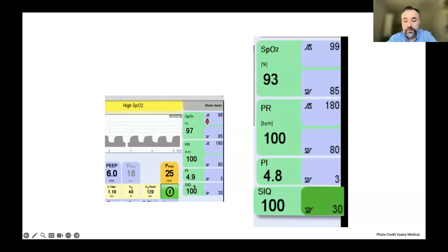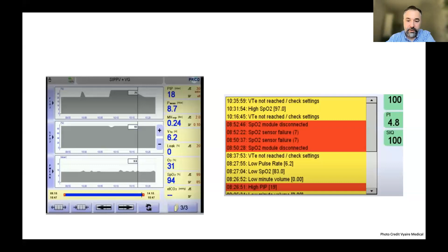This is the log of problems that can be potentially recorded by the ventilator. So if there are some problems, you can check that retrospectively, and it's also helpful to look at the trends. Here you can see the trends of the FiO2 and the SpO2. A lot can be checked versus other parameters that are being monitored during the ventilatory support.